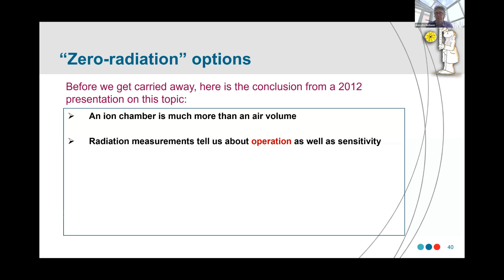So if we're not providing that confidence, what are we actually doing as a calibration laboratory? Only by making a radiation measurement can you determine that things are working properly, the detector's got the right connections, it's not failing in some way. We've got a history on this device over years that it's not changing, that a mechanical or a CT measurement would not pick up. And ultimately, we are telling the end user that the device will work in its intended environment. And if we're not doing measurements, are we really doing metrology? I think these techniques of CT and FEM have a role, and we see that in publications and in reports to CCRI meetings, but I think it's complementary rather than replacement.